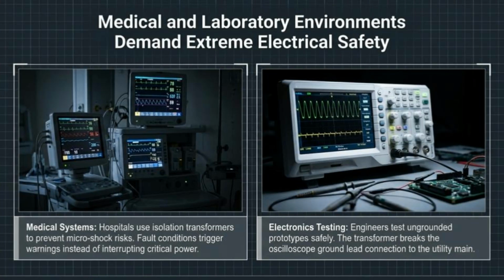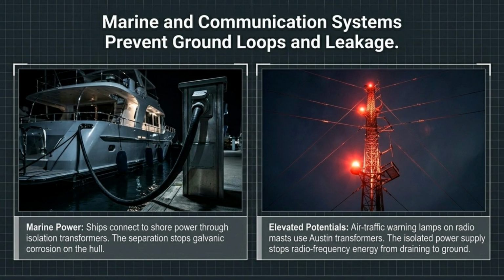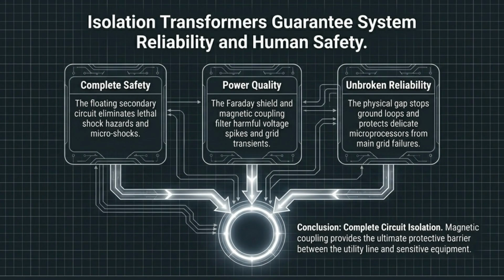Medical and laboratory environments demand extreme electrical safety. In medical systems, isolation transformers prevent microshock risks. For electronics testing, they safely break the ground connection, allowing engineers to test ungrounded prototypes. In marine systems, isolation transformers prevent galvanic corrosion when ships connect to shore power. In communication systems, they prevent radio frequency energy from draining to the ground, as seen in air traffic warning lamps on radio masts. Isolation transformers ensure system reliability and human safety through complete safety, enhanced power quality, and unbroken reliability. The ultimate protective barrier between the utility line and sensitive equipment is achieved through complete circuit isolation and magnetic coupling.